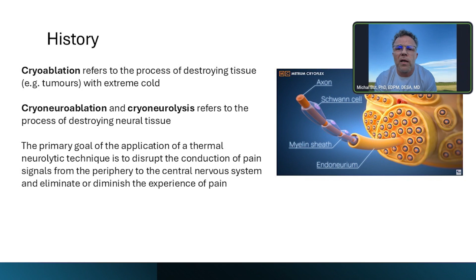And what is used in modern devices? We use the Joule-Thomson effect, where pressurized gas is transmitted to the small inner tube, and it goes through a very small hole at the end of the tube, and expands into the outer tube. And this reaction is endothermic. The temperature close to the active tip of the probe drops significantly, and depending on the gas used in the probe, you can achieve minus 80 degrees for nitrous oxide and minus 60 degrees for carbon dioxide. So you are able to stop the conduction completely, because the total stop of conduction is at minus 20 degrees.